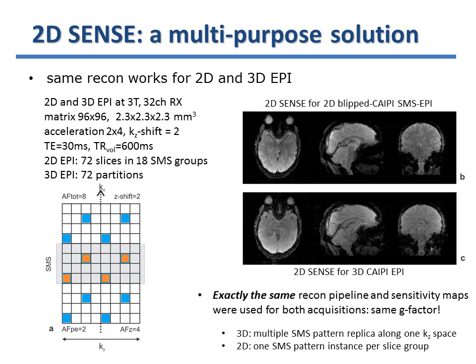Finally, we applied exactly the same reconstruction pipeline for blipped CAIPI EPI and volumetric 3D EPI. For matched field of view and CAIPI shift, the blipped CAIPI sampling pattern is a subset of the 3D EPI k-space coverage. This implies that exactly the same voxel locations fold onto each other, which yields identical g-factor maps for the volumetric and blipped CAIPI acquisitions. This demonstrates the flexibility of the 3D k-space-based representation of SMS sampling.